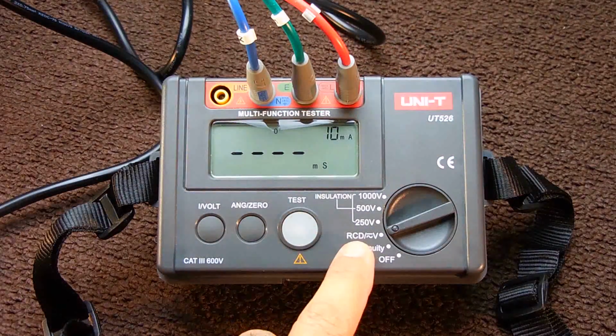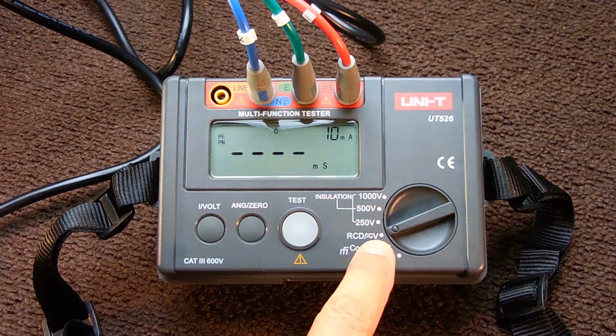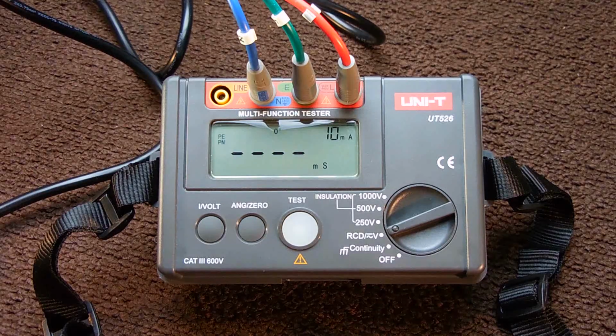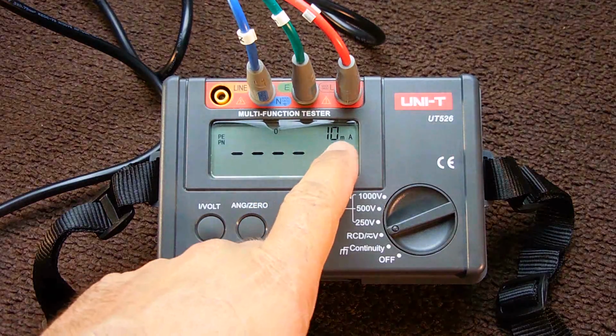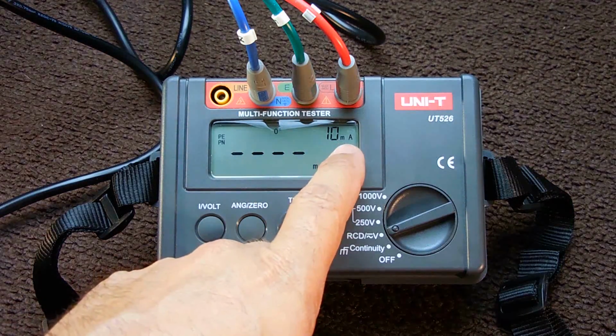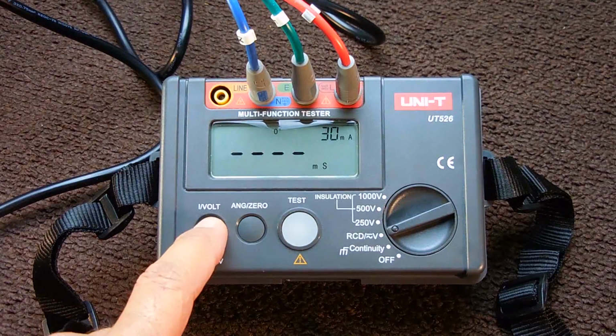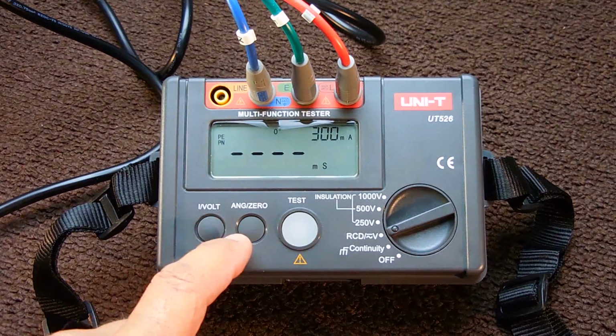Also on the RCD setting is the other feature that I mentioned that I do not use, and that is for testing residual current circuit breakers, or GFCI type circuit breakers. What you do is you set the trip current. Here it's 10 milliamps. You can make it 30, 100, or 300.